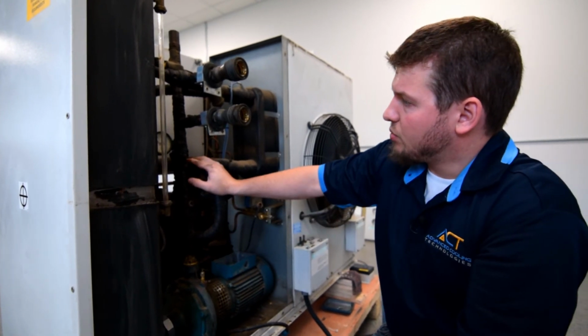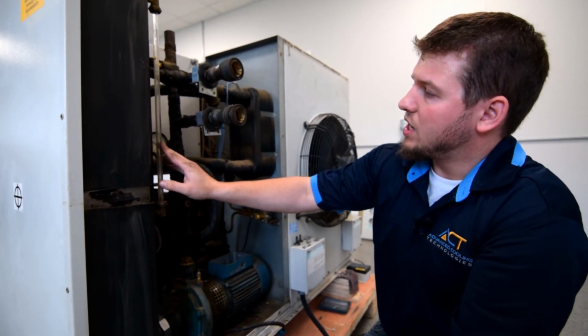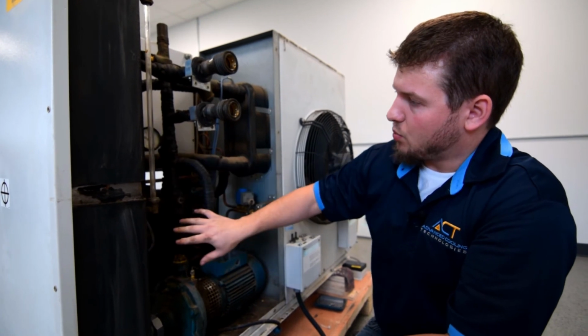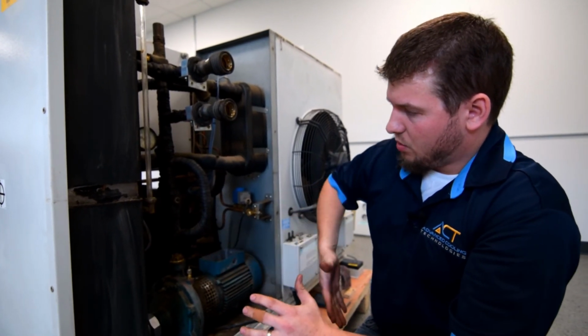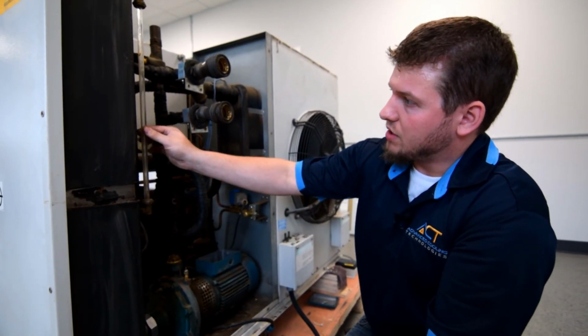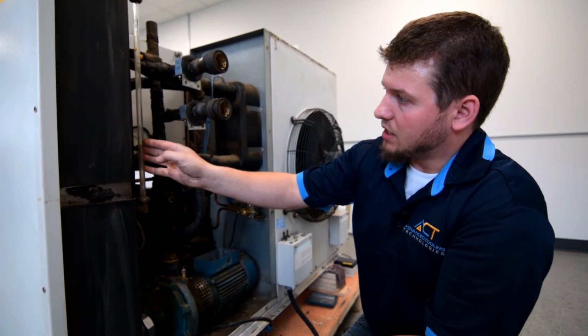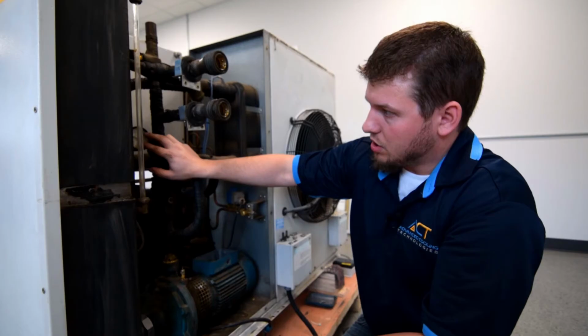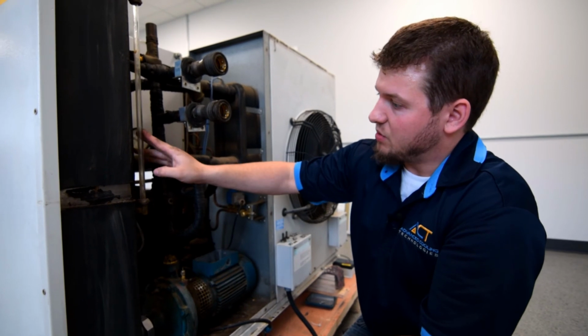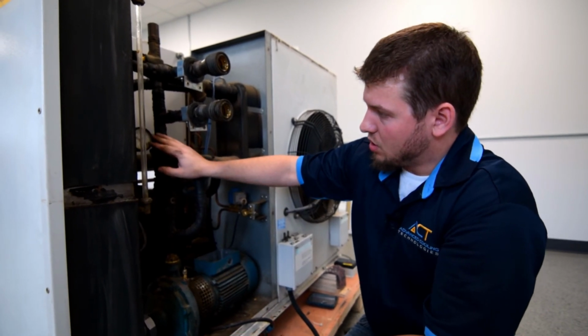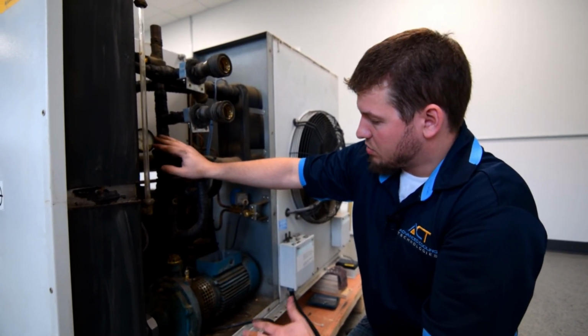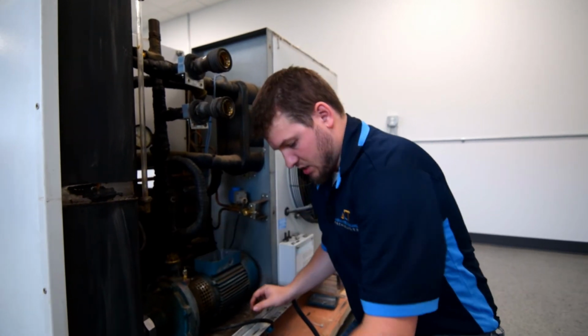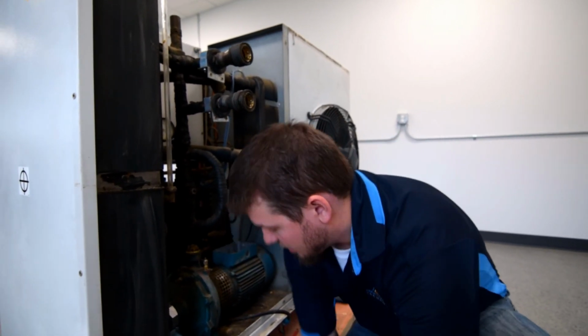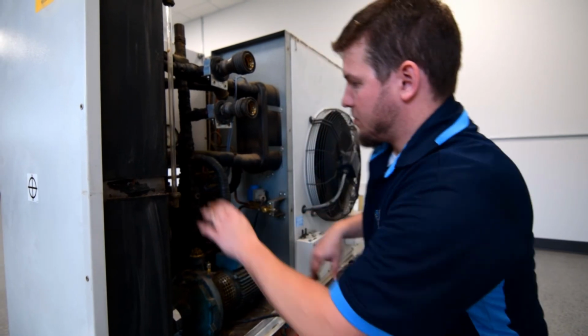I do want to say that we need to take precaution when we take out this pump. As we're taking it out in one piece, we're going to have to kind of twist it out, and we're going to take extra caution around this sight glass. This is a glass sight glass, and this pressure gauge here is prone to hitting it, and when it hits it, it shatters. So when we're taking this out, take extra caution and watch this sight glass to make sure you don't hit the pressure gauge or the sight glass.